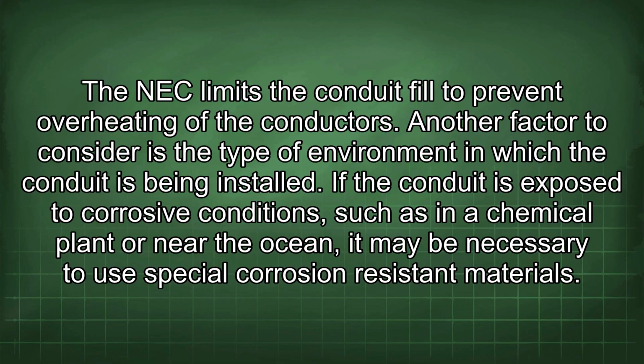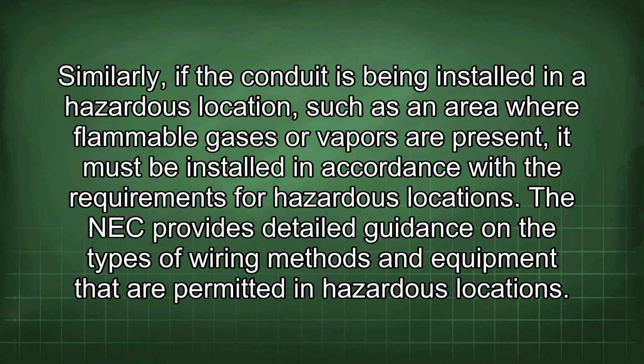Another factor to consider is the type of environment in which the conduit is being installed. If the conduit is exposed to corrosive conditions, such as in a chemical plant or near the ocean, it may be necessary to use special corrosion-resistant materials. Similarly, if the conduit is being installed in a hazardous location, such as an area where flammable gases or vapors are present, it must be installed in accordance with the requirements for hazardous locations. The NEC provides detailed guidance on the types of wiring methods and equipment that are permitted in hazardous locations.